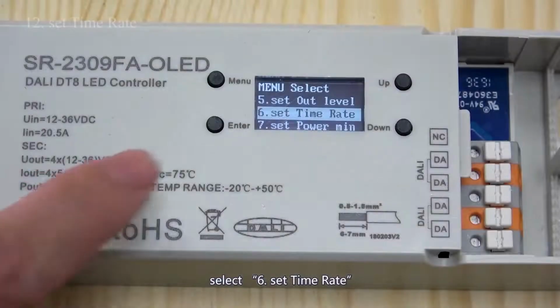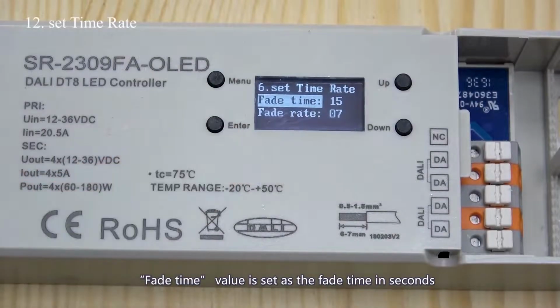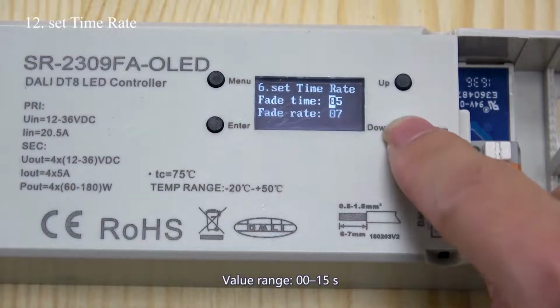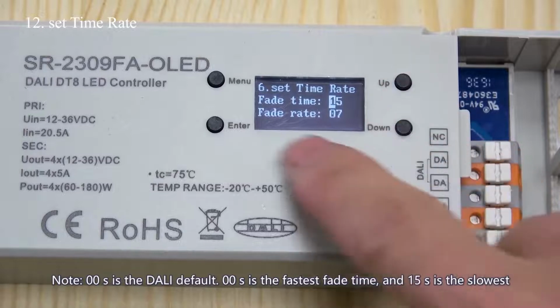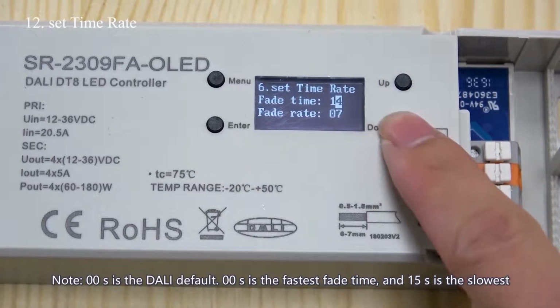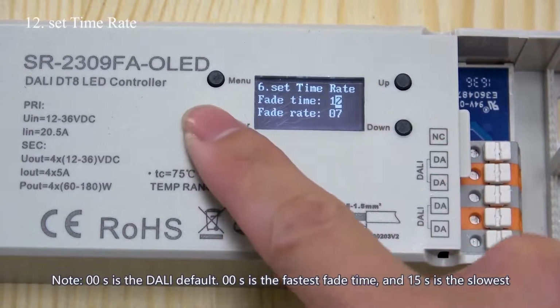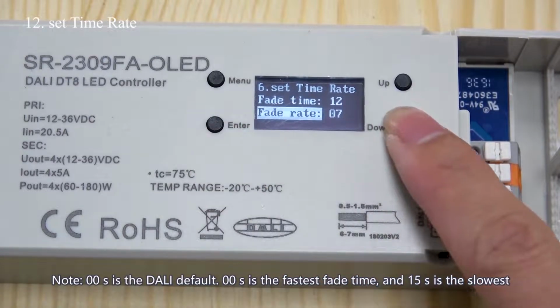Select 6. Set time rate. Fade time value is set as the fade time in seconds. Value range, 00 to 15s. Note, 00s is the DALI default. 00s is the fastest fade time, and 15s is the slowest.